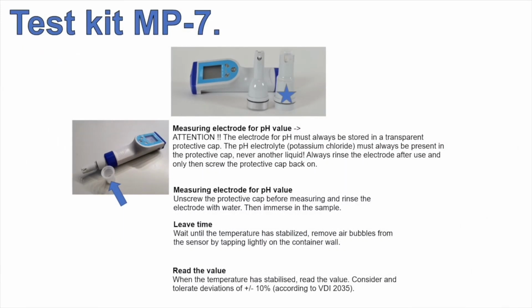Using the MP7 test kit for measurement of pH, the electrode for the pH must always be stored in a transparent protective cap. The pH electrolyte, which is potassium chloride, must always be present in the protective cap, never another liquid. Always rinse the electrode after use and then screw the protective cap back on.